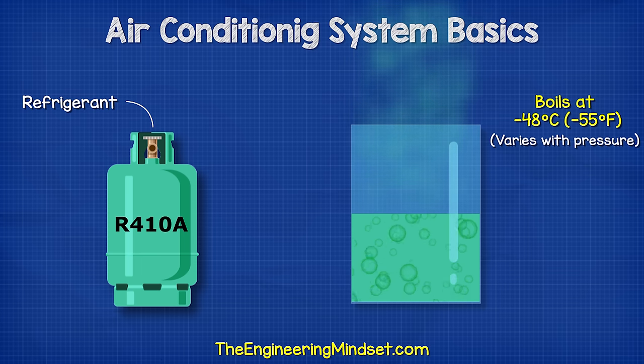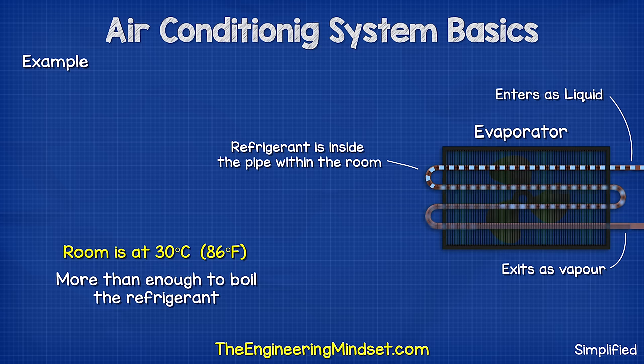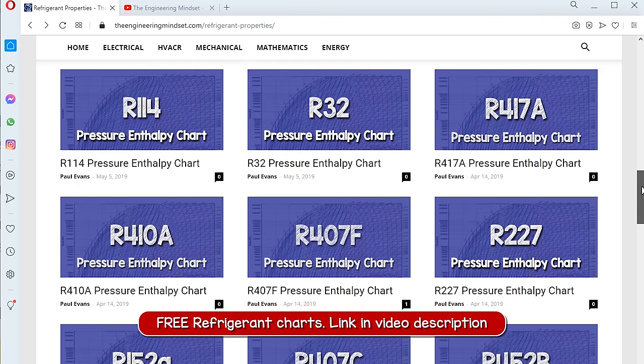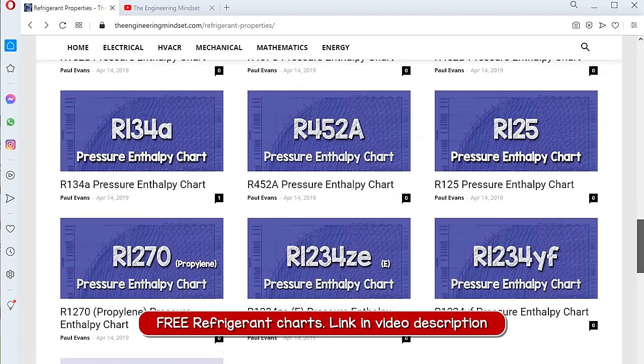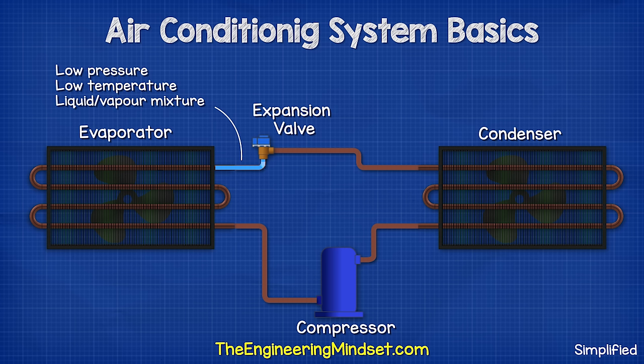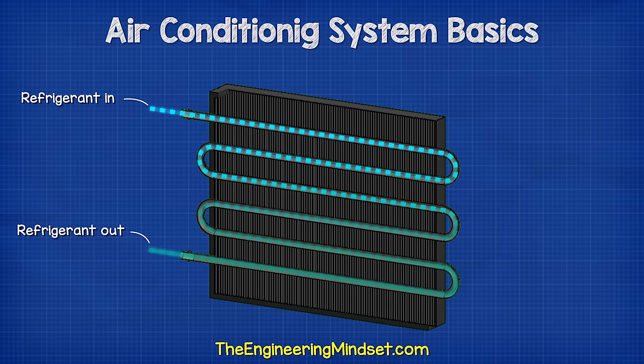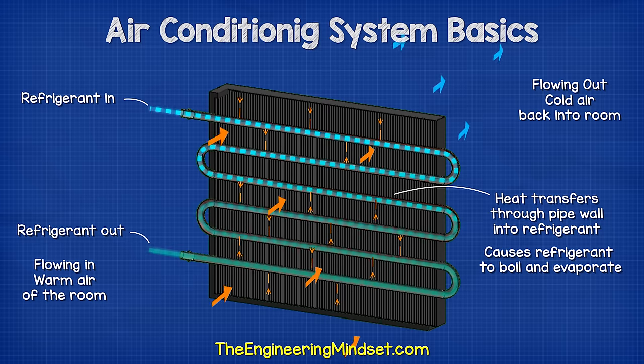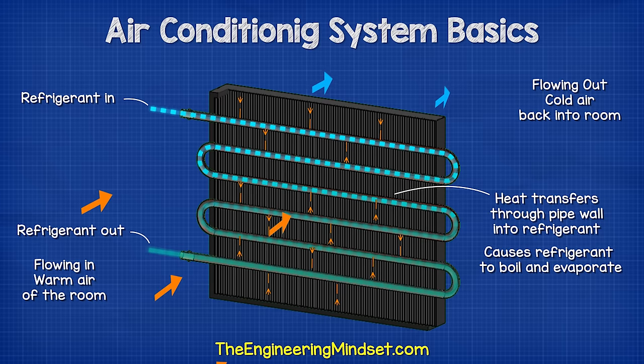But if the refrigerant is inside a pipe within a room and the room is at 30 degrees Celsius or 86 degrees Fahrenheit, then this will be more than enough to cause it to boil from a liquid into a vapour. So the refrigerant is entering the evaporator as a low pressure, low temperature, liquid vapour mixture. It flows on the inside of the pipe, and at the same time, a fan is moving the ambient air of the room over the outside of the pipe. This causes the refrigerant to boil.